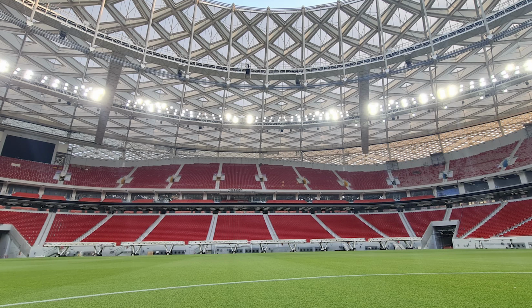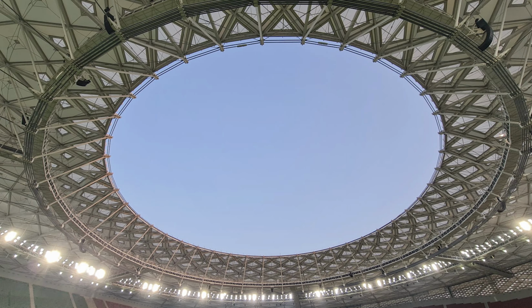We were involved with 3 of the Qatar 2022 World Cup Stadiums, most notably the World Cup final stadium, Lusail, which obviously we all saw on the telly. Really key, as it had internal both ventilation and air conditioning, so that was very difficult because we were ventilating all the occupants in the stadium, but in a novel way. So we weren't conditioning the whole space. We were just conditioning the space around the people, so it's more energy efficient.